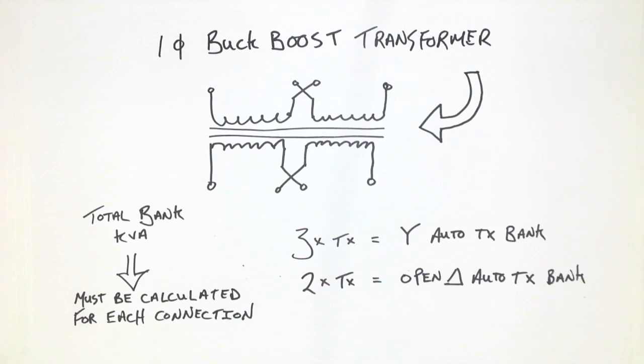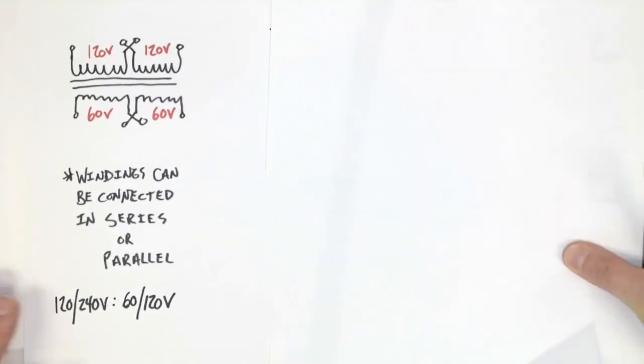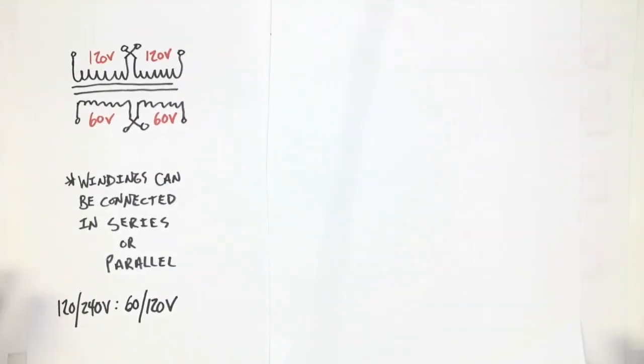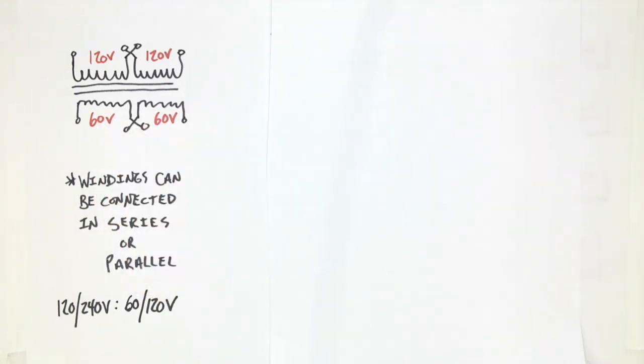Now, before we get too far, we need to have a good idea as to how the connections work on a buck boost transformer so that we can start determining what is necessary for the 3-phase bank connections. Here's a typical buck boost transformer. We have 120, 240 listed. That would be the windings in either series or parallel. And then we have 60, 120, and that would be the secondary windings connected in either series or parallel.